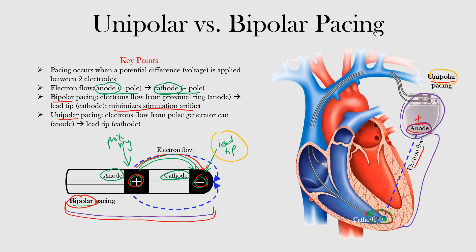With unipolar pacing, we are at risk of more stimulation artifact because the electrons have to flow a farther distance compared to bipolar. The anode is at the pulse generator and the cathode is at the lead tip, so the electrons must travel that whole distance, potentially picking up excitable tissue between the two and causing an artifact on the EKG.